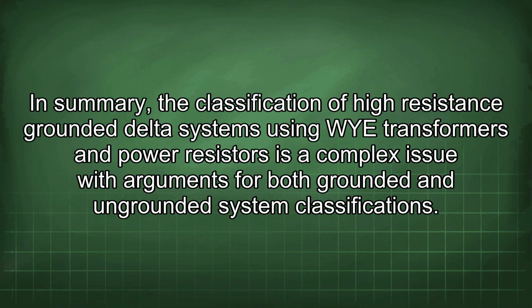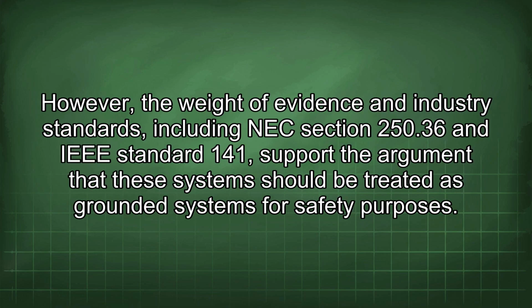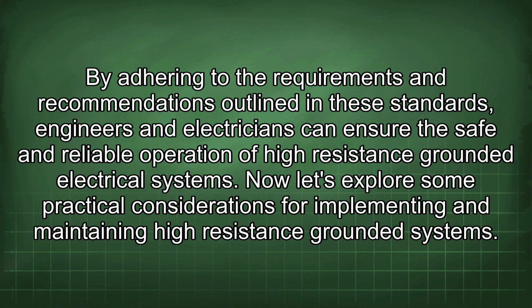In summary, the classification of high-resistance grounded delta systems using WYE transformers and power resistors is a complex issue with arguments for both grounded and ungrounded system classifications. However, the weight of evidence and industry standards, including NEC Section 250.36 and IEEE Standard 141, support the argument that these systems should be treated as grounded systems for safety purposes. By adhering to the requirements and recommendations outlined in these standards, engineers and electricians can ensure the safe and reliable operation of high-resistance grounded electrical systems.